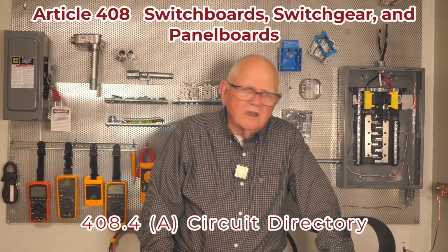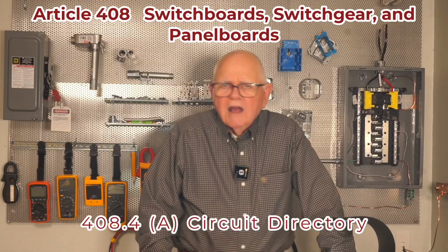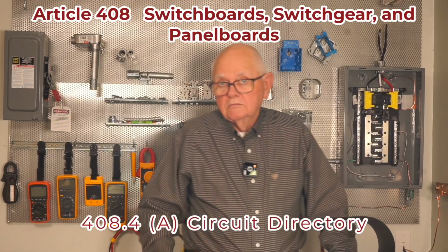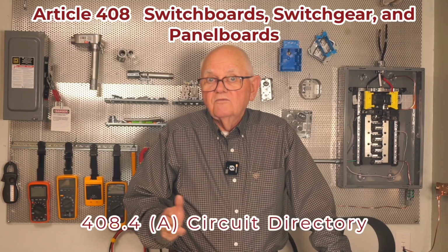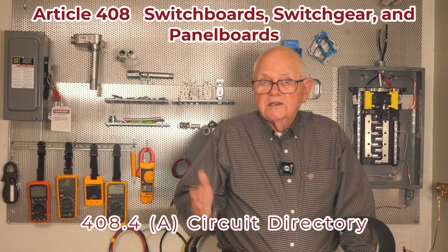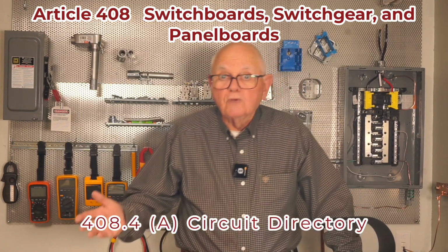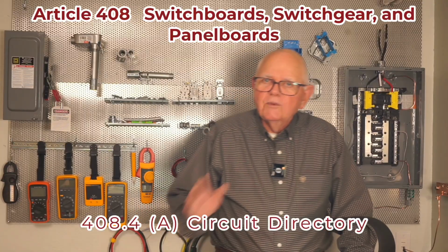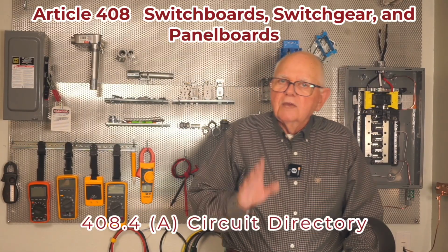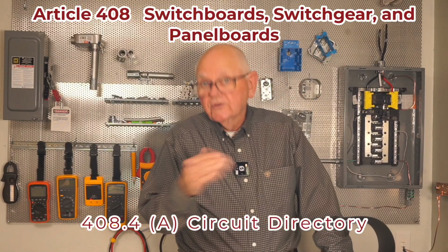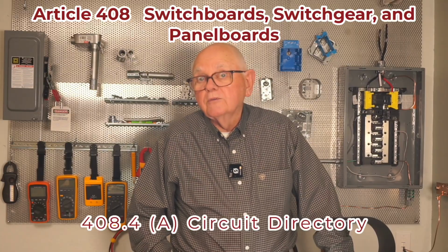It says, hey, look, don't make them generic. I can't put on my circuit directory, kid's bedroom. Why? Because 5 years from now, the kid's bedroom will be Charlie's bedroom or whatever, okay? So we can't use that generic marking. It would need to say something like receptacles, northwest bedroom or whatever. That would be maybe a good one.